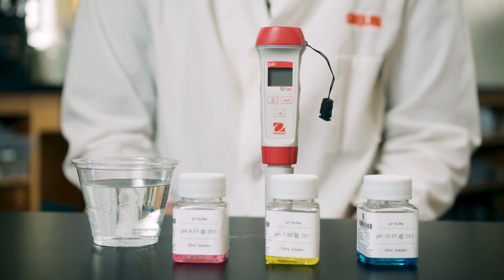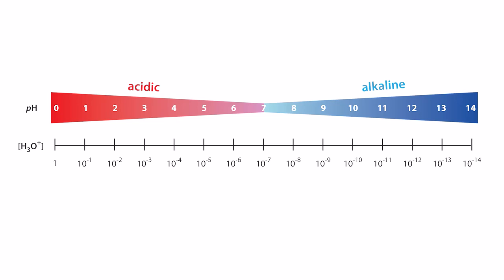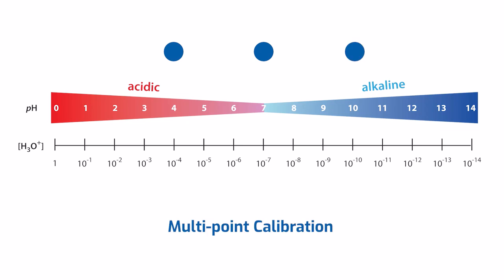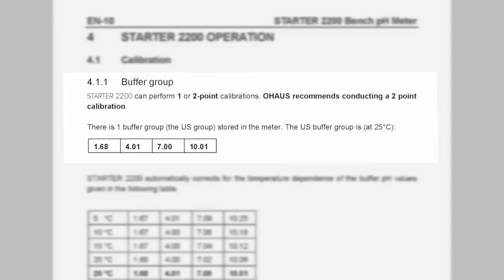Many modern pH meters are factory calibrated and do not require initial calibration. However, over time, many models do require periodic calibration to ensure accuracy. You may wish to calibrate your meter after extended storage or when extreme accuracy is important. There are 3 different types of calibration when it comes to pH meters: single point, 2-point, and multi-point calibration. These names refer to the number of points or pH values at which a calibration is performed. The greater number of calibration points, the greater the accuracy of the calibration. These types of calibration are conducted using buffers of known pH values. Refer to the instruction manual for your pH meter for the buffer solutions that you should use.